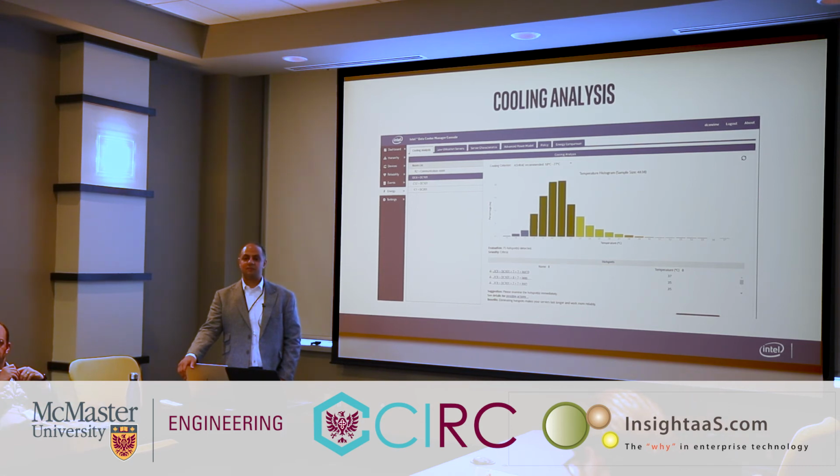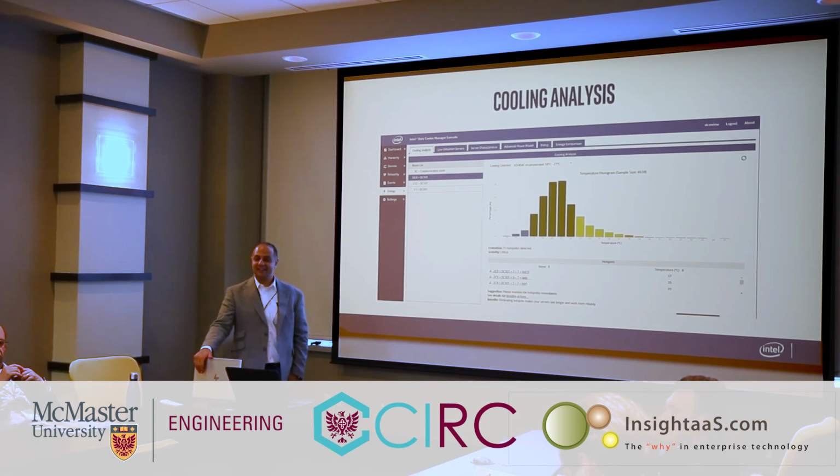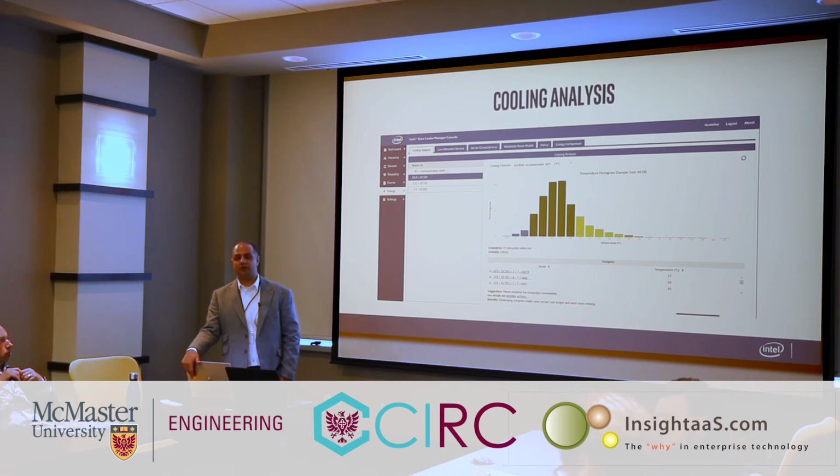What can we change in a server when you shut it off? It would block the fan, so the spaces that the fan creates, so heat cannot recirculate. If you take that server out, that problem goes away, and you put a blanking panel on. I should have been more accurate and said shut it down and take it out. You can take it out, but shutting it down only, you're absolutely right. It causes more problems, not least because it's still pulling power.